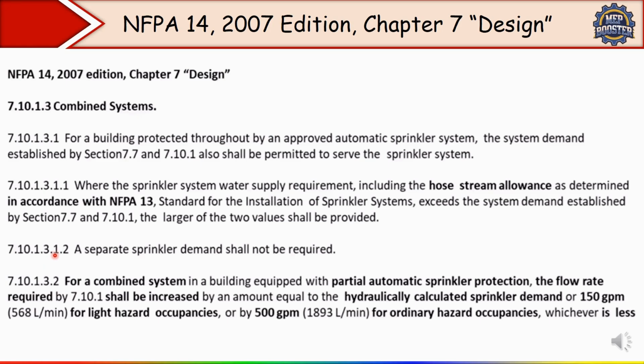Correct? So instead of separate piping for sprinkler and standpipe, the system is designed to serve both from a common water source. Okay, that system is called a combined system. Now here the important thing: how you can find out the flow for a combined system, how much GPM. This is the important factor. So here the point is written.